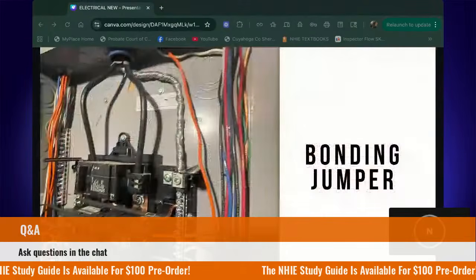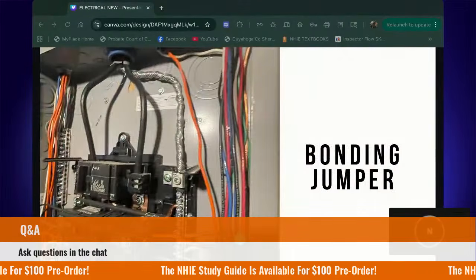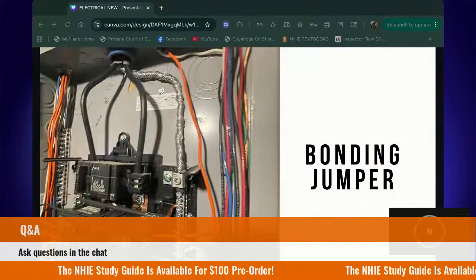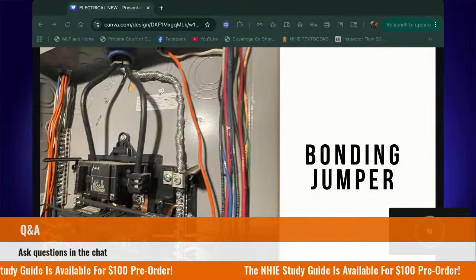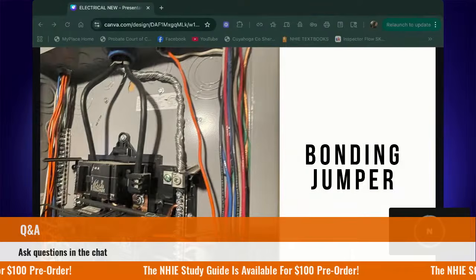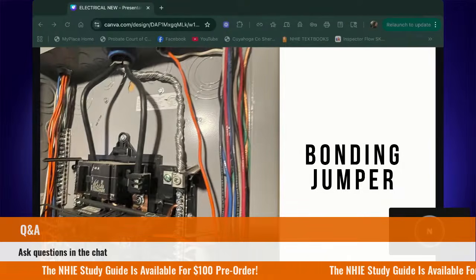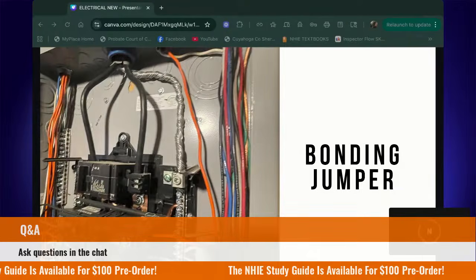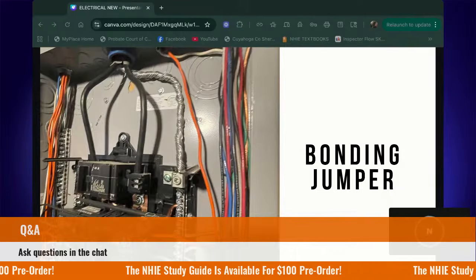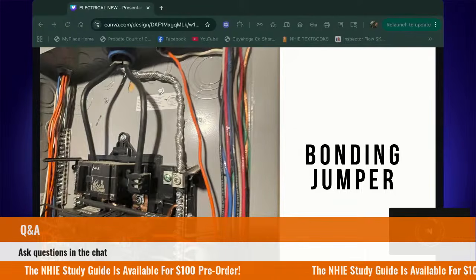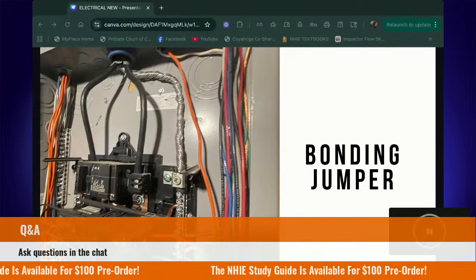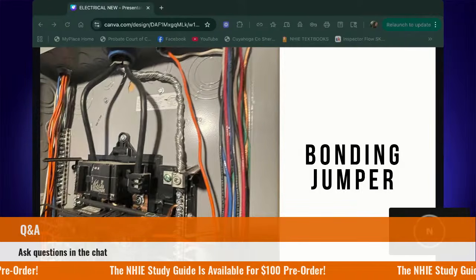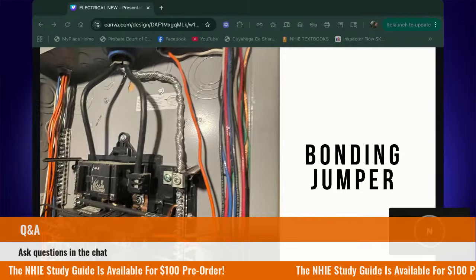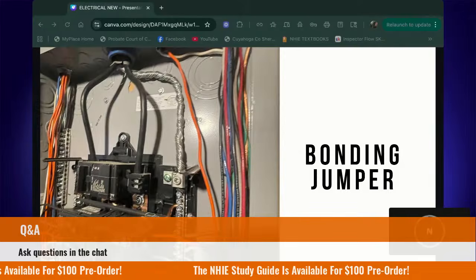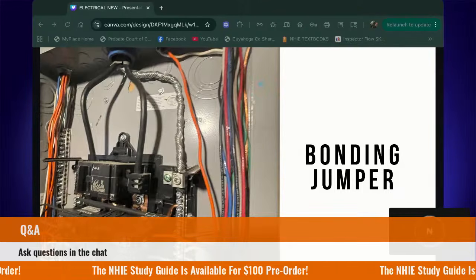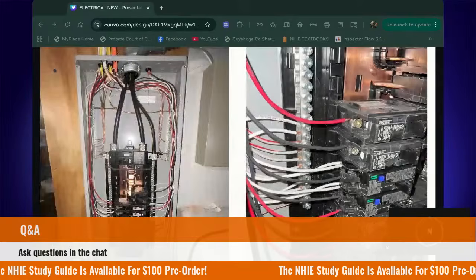Next inside of your panel is the bonding jumper. The bonding jumper is just a connection point inside the panel that connects the neutral bar to the ground bar. Just write that down in your notes so you have it. We're about to make it plain in these next couple of slides. The bonding jumper is a metallic connection, so it's a metal connection inside of the panel. It connects the neutral bus bar and the grounding bus bar.